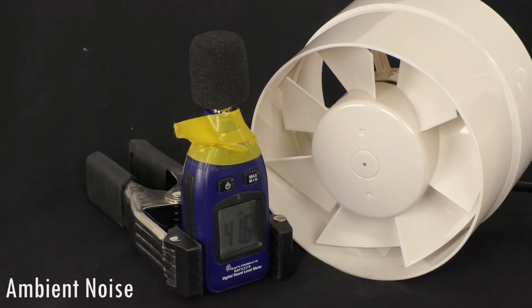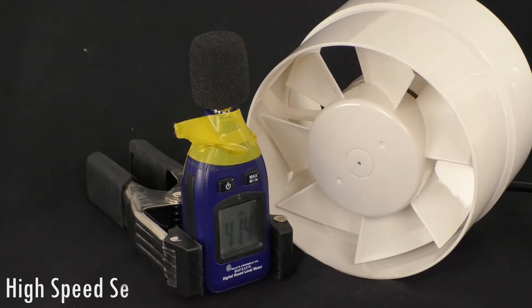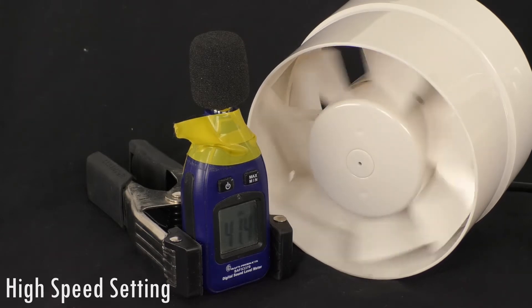The ambient noise in the building was 41.5 decibels. When the fan speed is turned to high, the noise level changes to 47.5 decibels.